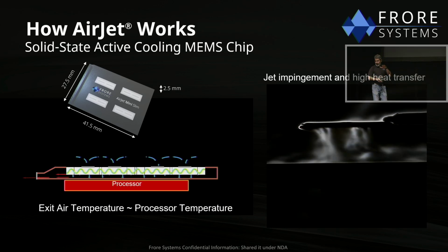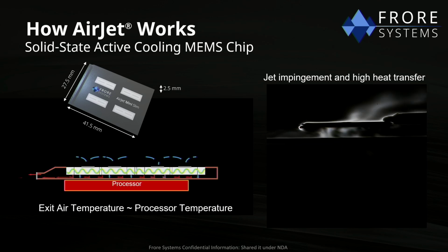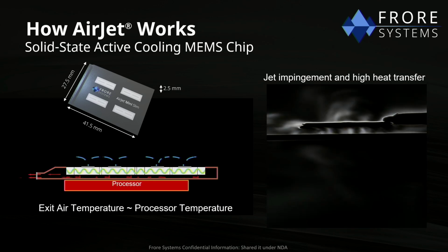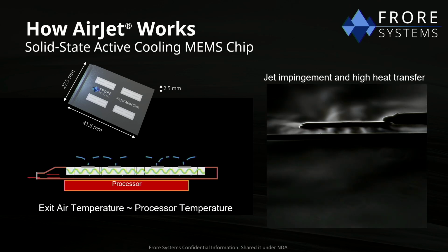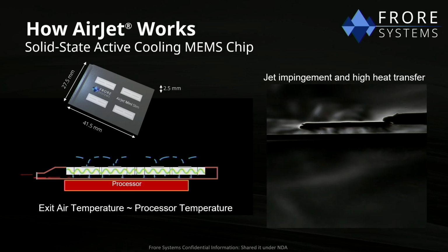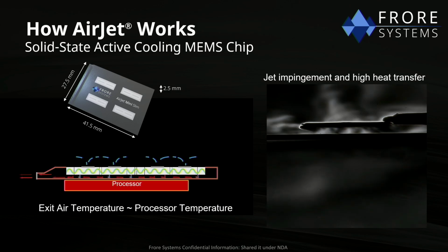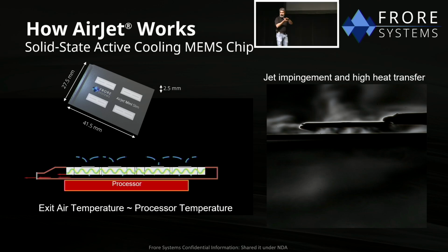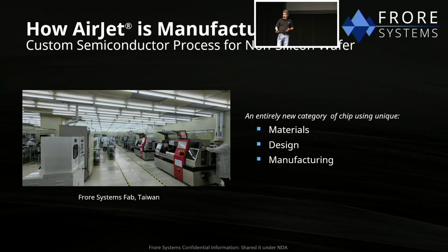Right? So you've saturated the air with all the heat it can take. Now, the other thing that happens is how the jet comes out. This is a Schlieren image. You can see the jets coming up. As this plate was moved up, you could see how the impingement happens. And this we have stopped because for visualization, it's better to stop it right here. This goes all the way to 300 microns. Okay? And that's where the actual impingement happens. The boundary layer gets reformed every cycle at the 24 kilohertz in the array underneath, and the exiting air is saturated.